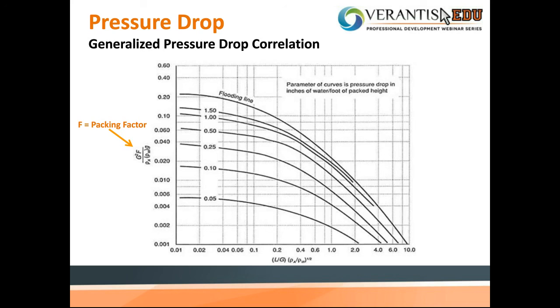A more rigorous standard pressure drop correlation you'll find in a lot of chemical engineering books will include additional parameters for viscosity, for density of a specific liquid compared to water, because for example, in many applications you might be scrubbing with an alcohol or a solvent, and your gas might be at higher pressure, which would mean increased density. Or in some cases, lower pressure if you're at elevation and temperature.